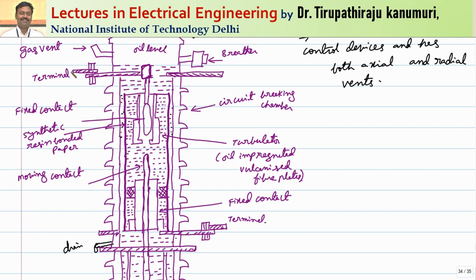The terminals are taken inside and connected to the fixed contact. The fixed contact is attached to the turbulator, which is nothing but the arc quenching chamber — this is where the arc will be extinguished. The turbulator is made of oil-impregnated vulcanized fiber plates. These plates are porous, meaning they can allow oil to enter from outside into the turbulator or exit when pressure changes. They have vents in both the axial direction (toward the top) and the radial direction, and these vents open only when pressure increases.